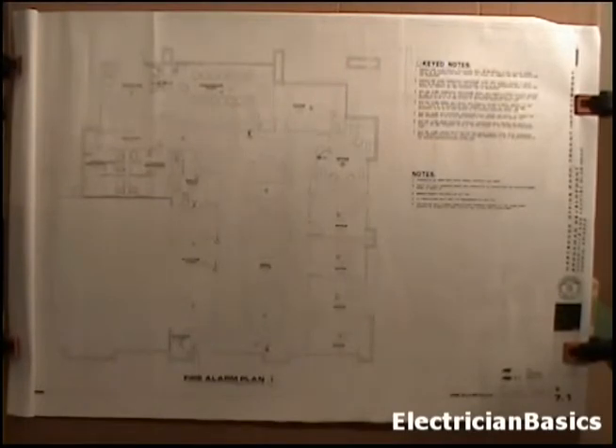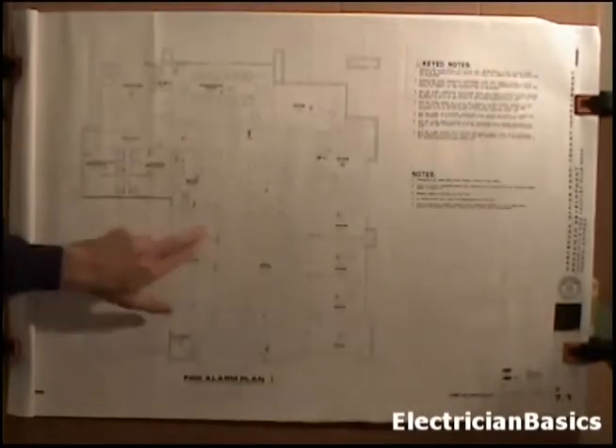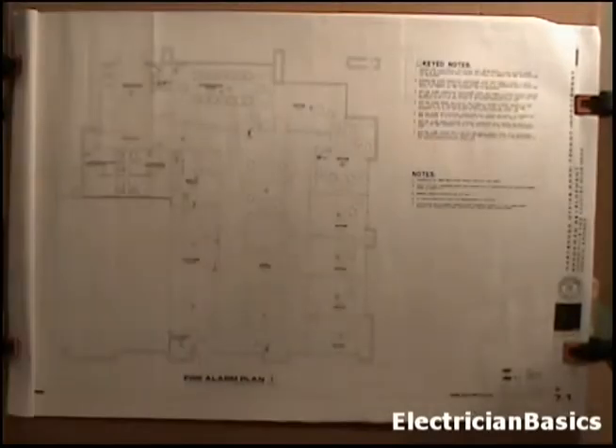Contractor shall provide and install all conduit and wire necessary to tie in the new devices to the existing control initiating device loop. On the mechanical print, it had a different symbol for that. It was like an S for a smoke damper. So here we have slightly different symbols with different trades, but we spoke about these earlier. And remember, those devices were actually supplied by the manufacturer of that equipment, and all that the electrician would have to do would be to run the wire to those and hook those up.